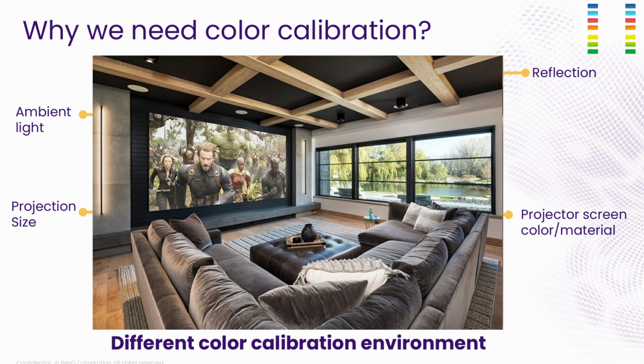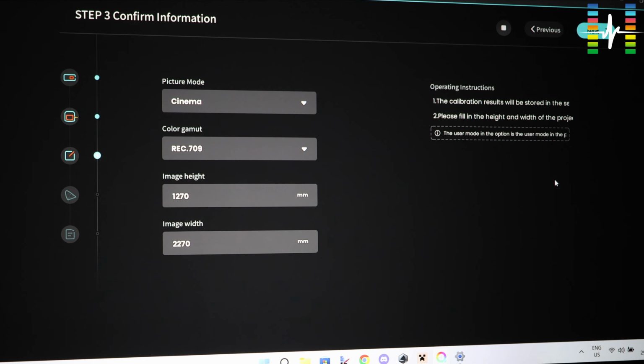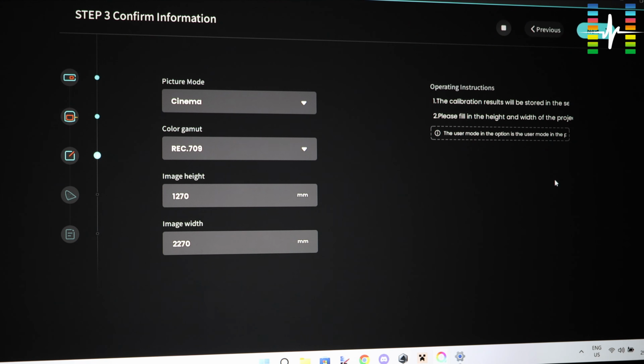So with all this combination, we call this the environment factor, which when calibration kicks in, it will handle all these environment factors and will be able to achieve a better color accuracy. And what they claim is that it can be as low as below 1%. Is that true? Now we're going to show you the calibration in a short while and we'll find out.